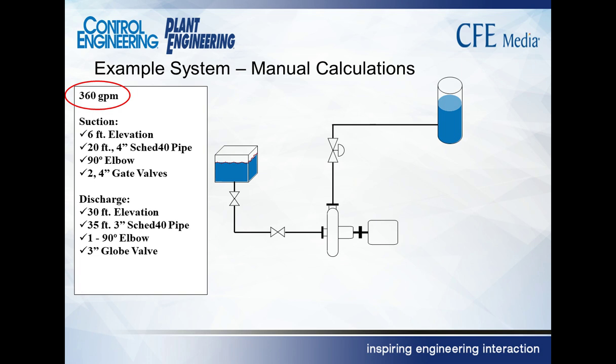It has 360 gallons per minute as the design. That's what this particular operation needs. They need 360 gallons per minute. There's a suction tank that's above the pump, so there's a little bit of head, a little bit of pressure coming into the pump. And then there's a discharge tank that's much higher. It's going to pump the liquid out of the suction tank up into the discharge tank. Okay? So typically when you set up a system curve, you evaluate all of the suction side parameters or elements, and then you evaluate all of the discharge elements, and the total dynamic head is discharge head minus suction head.